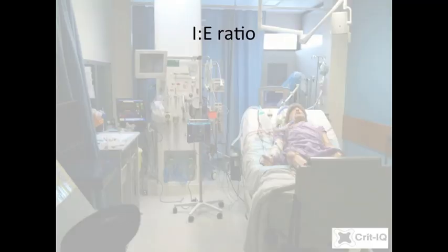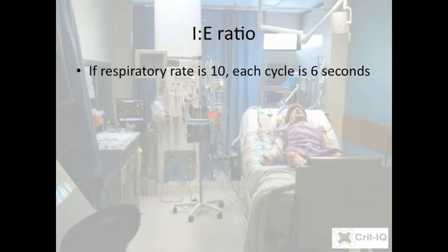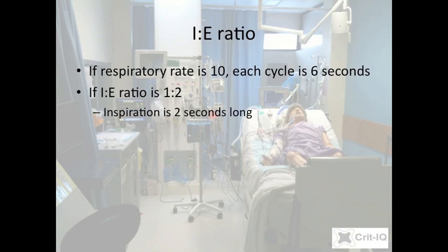Here's how it works. If you have set the respiratory rate to 10 cycles per minute, each cycle has to occur in 6 seconds. If the IE ratio has been set to 1 to 2, then in that cycle, inspiration will occur for 2 seconds and expiration will occur over the next 4. Ventilation with a set volume will need to occur within the inspiratory time, so the shorter the inspiratory time, the faster the inspiratory flow will have to be.